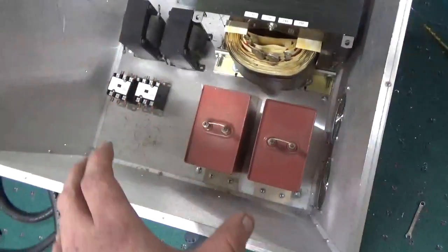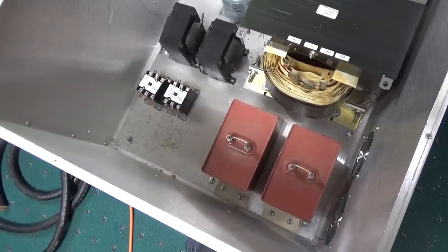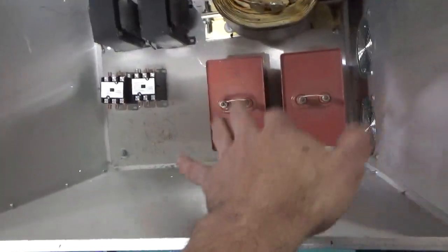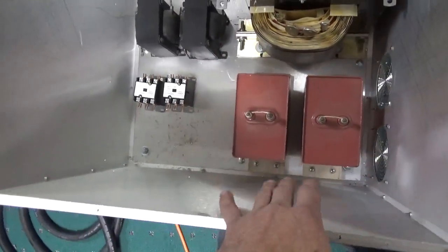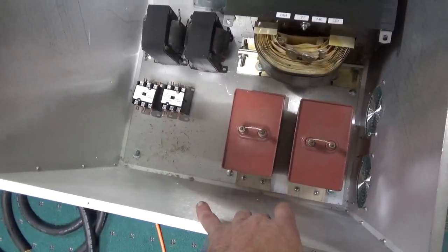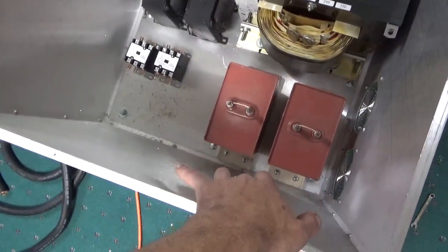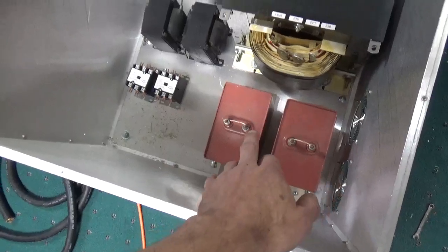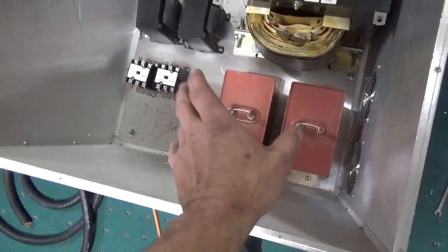I've never had a problem with one of these caps, but if I did or if the customer did, the whole assembly can come out. You also have to have resistors across each one, so I'm using four resistors for this amp. They'll be mounted on the wall, they're 100k each, so 400k total. The center of the resistors has to be tied to the center junction point, so basically two resistors per cap across each cap so the voltage is equal among each one.